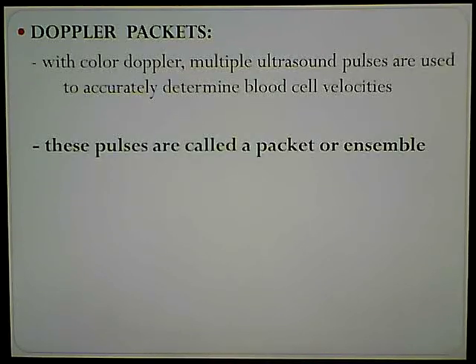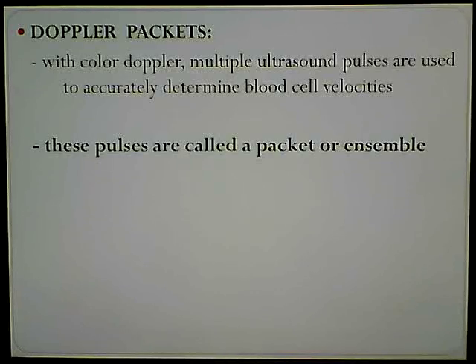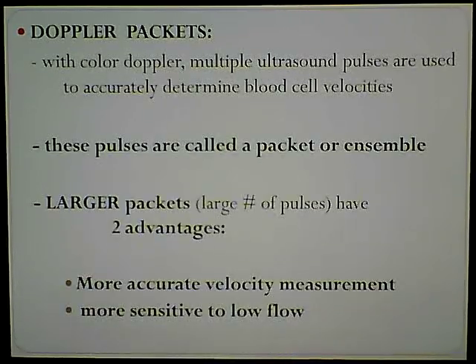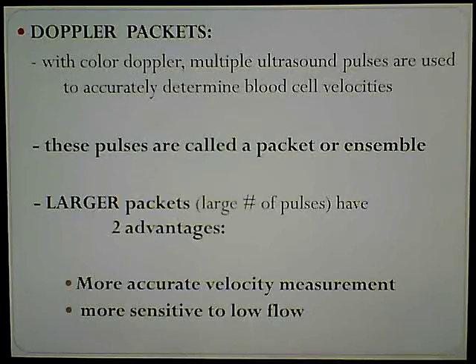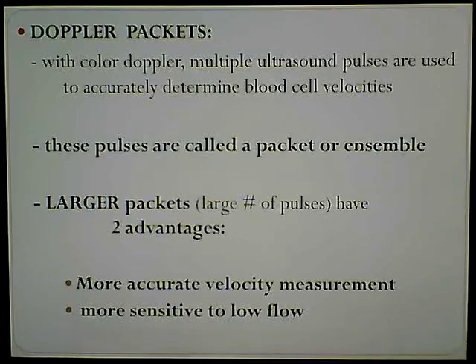Doppler packets - this is kind of like how much information we want to use to determine these blood cell velocities. With color Doppler, multiple ultrasound pulses are used to accurately determine blood cell velocities. These pulses are called a packet or an ensemble. The larger the packets, or large number of pulses, have two advantages: we get more accurate velocity measurements, and it becomes more sensitive to low flow the larger the number of pulses in these packets.